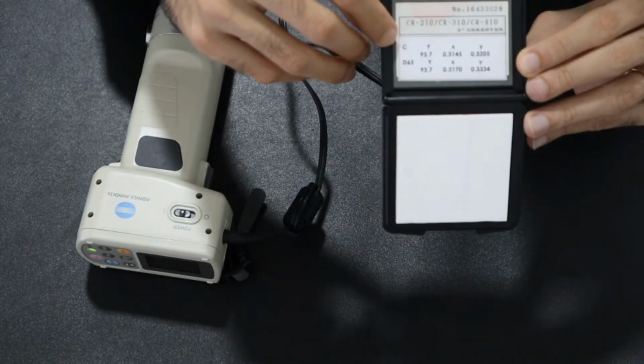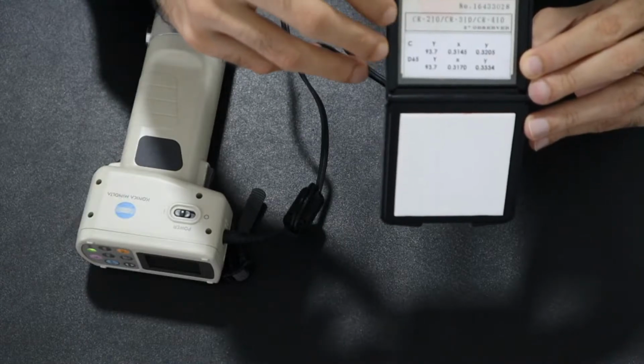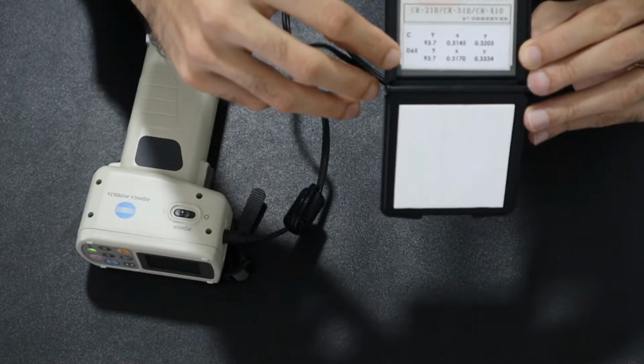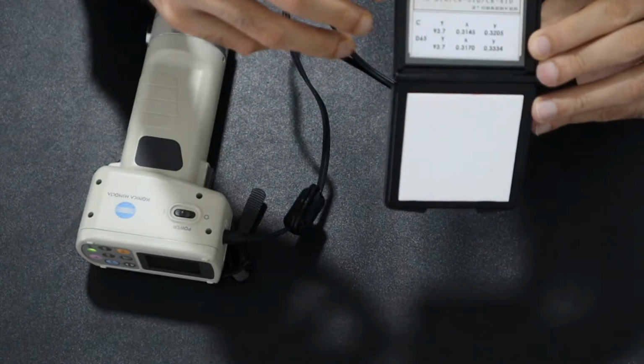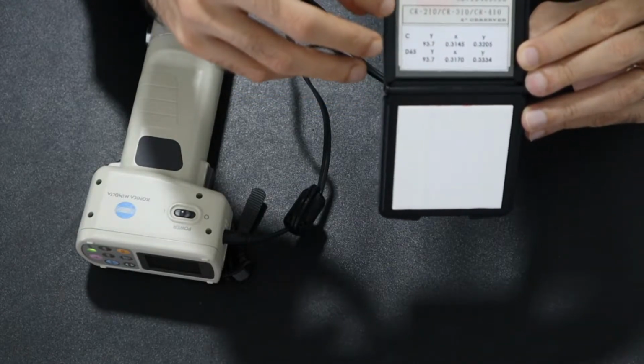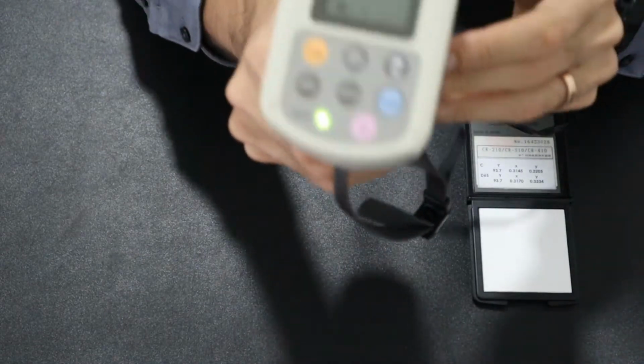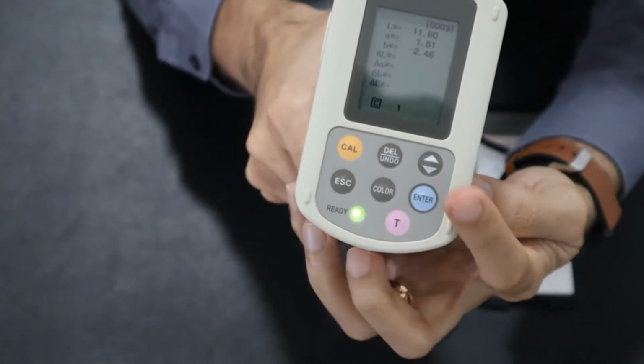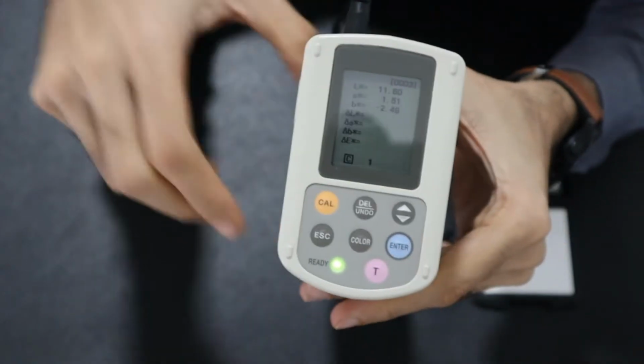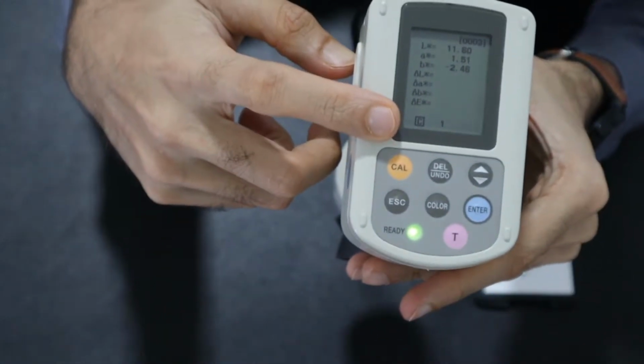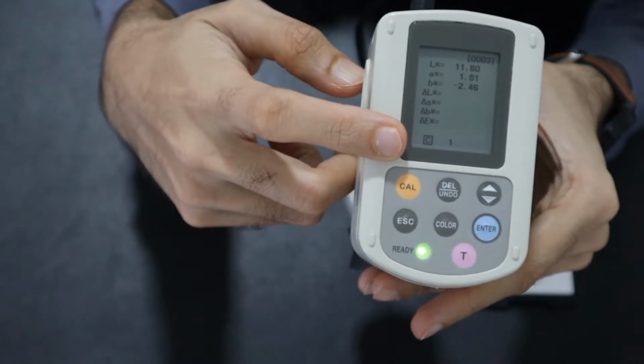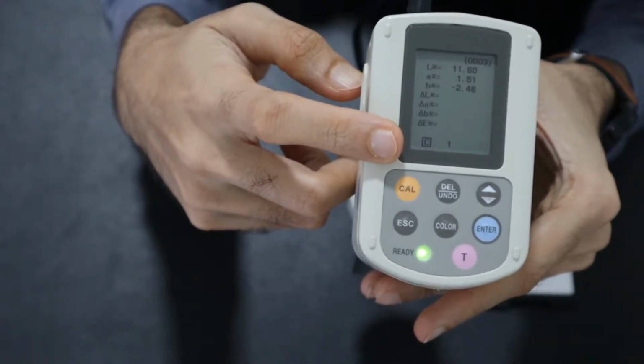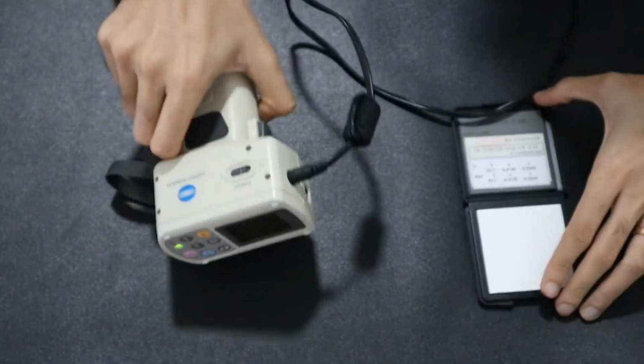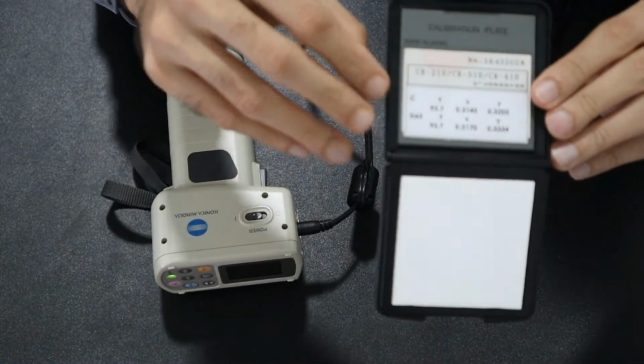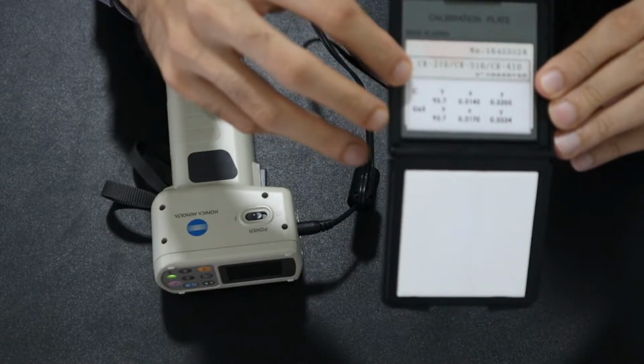It will be very important to know whether you need to make measurements in C illuminant or D65 illuminant. In order to know which one the equipment is currently set to, you could have a look at the bottom part of the equipment here. Over here, if it's written C, that denotes C illuminant, or if it's written D, it would be for D65 illuminant. Since this equipment is set to C, I will ensure that the equipment calibration data follows the C illuminant.